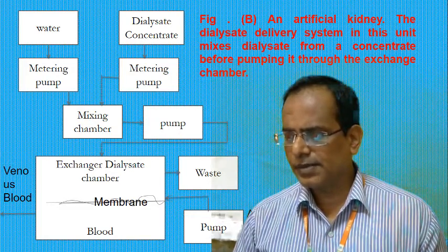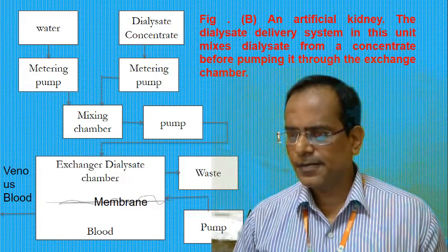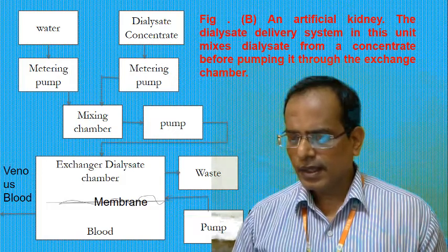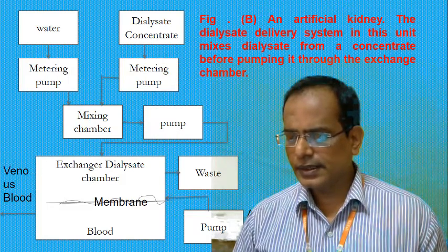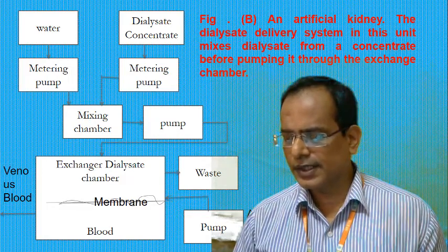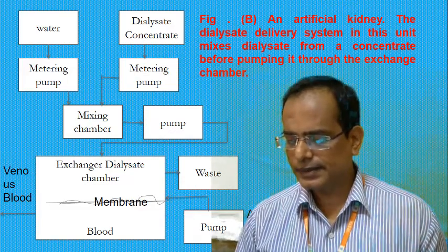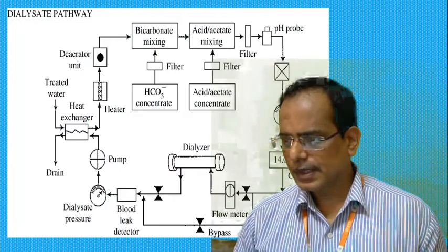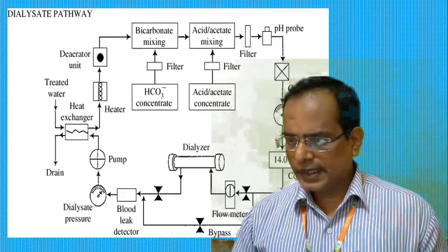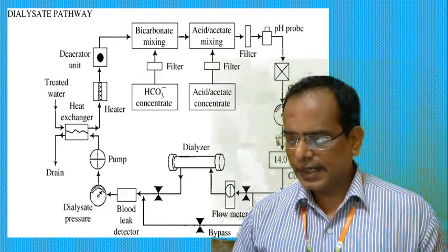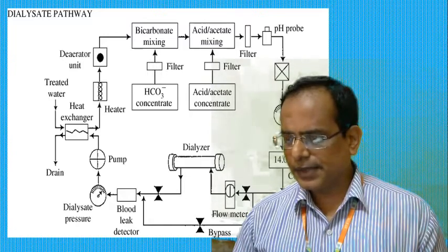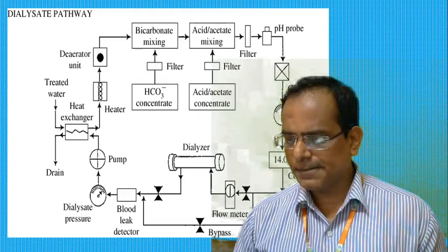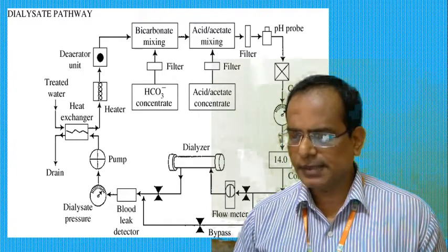Optical systems are used to detect the leakage in order to prevent it. In addition, instruments monitor the pressure in the blood component to rapidly detect any abnormalities, such as major leaks or clotting phenomena that might change the pressure.